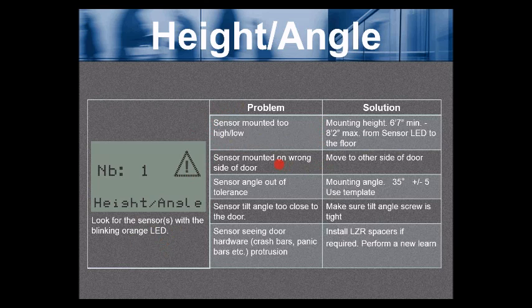If you see the sensor and the arrow is pointing up toward the header, you've mounted the sensor on the wrong side of the door. The next possible problem is the sensor angle is out of tolerance. The mounting angle is 35 degrees, plus or minus 5 degrees. You should be using the template that's supplied with the installation kit. That will ensure you'll be successful in that mounting angle.